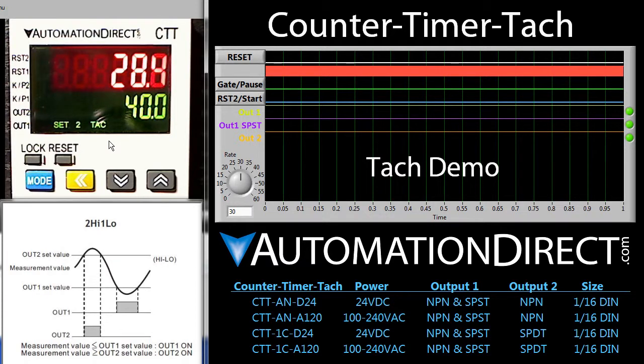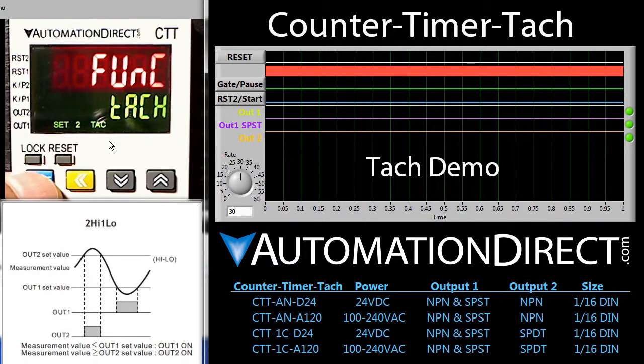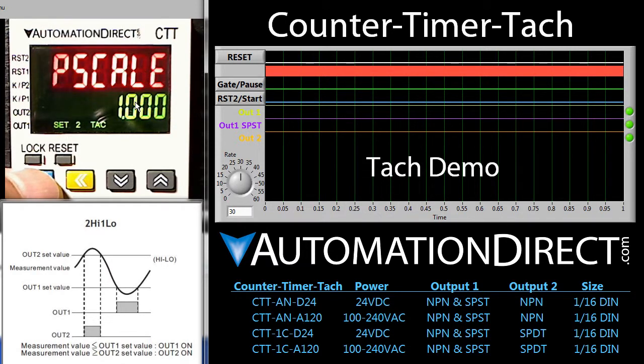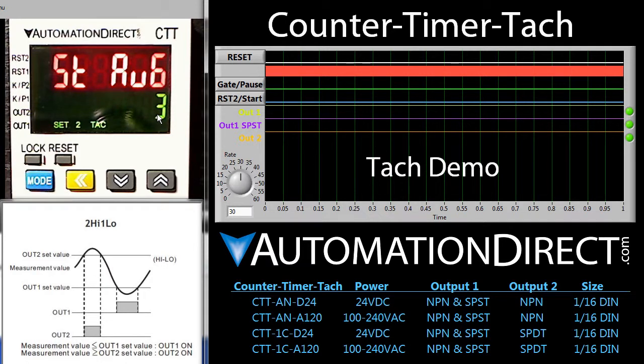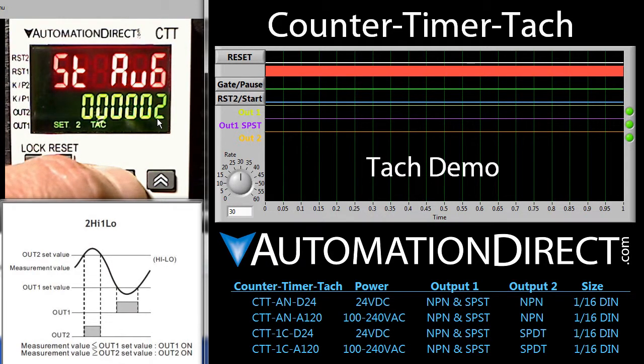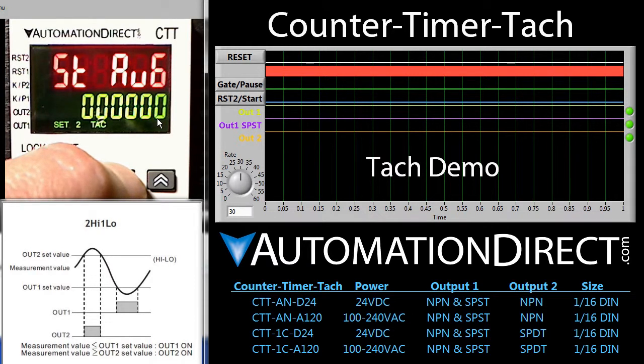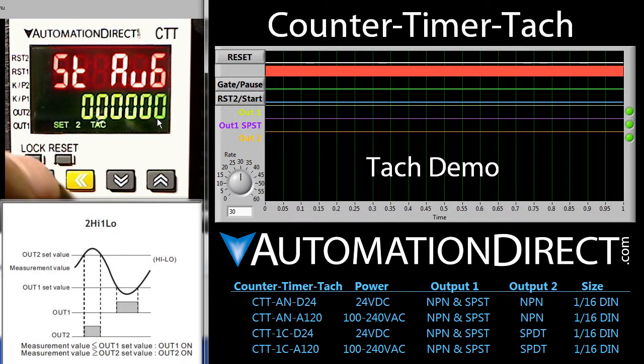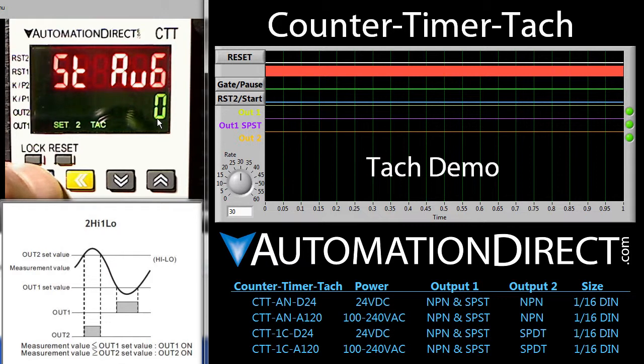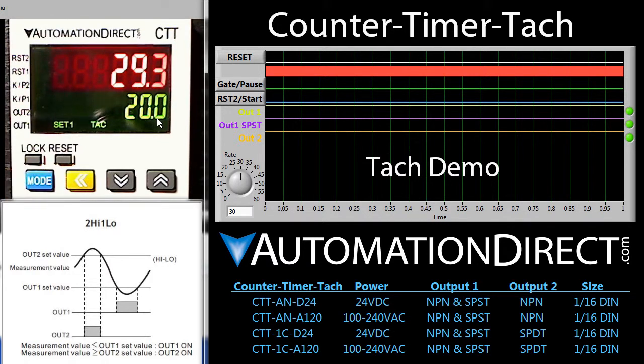Let's go turn that off and see what happens. I'm going to hold down the MODE key for 3 seconds and that will get us into the configuration mode, and then I'm going to punch the MODE key several times to bring up that parameter where we set averaging. And there it is. The averaging parameter is currently set at 3 – that means to average 8 points before making a decision. We're going to change that – a 2 would be 4 points, a 1 would be 2 points, and we're going to put a zero in that says average no points – just take each sample and make a decision. I'll lock it in by pressing the MODE key, then hold the MODE key down for 3 seconds to flip us back into the operating mode and now we're running.